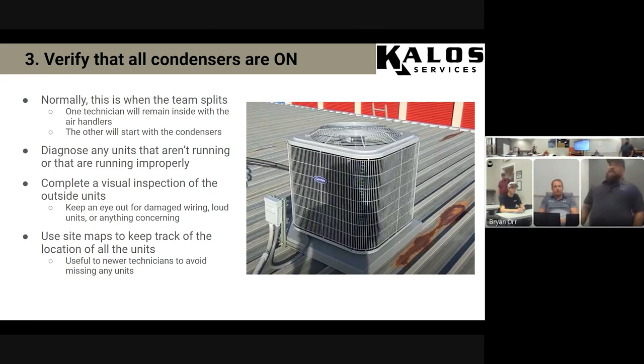Maintenance, like any service call, you want to keep your eyes open for everything — anything that aesthetically doesn't look right that the customer could point out, like dirty return grills. You may look at a scope and say that's not part of my scope, but if it looks bad and clients can see it, that's something you should address. Sometimes addressing it means it's well out of scope and they're going to have to pay for it. Sometimes it's easy enough just to take care of — something like a dirty return grill, just take care of it. Pay really close attention to freezing and moisture, both active issues and signs they've been occurring.